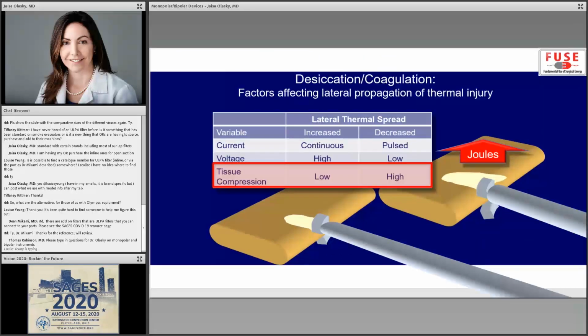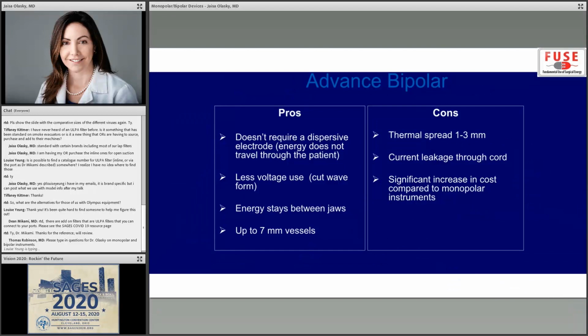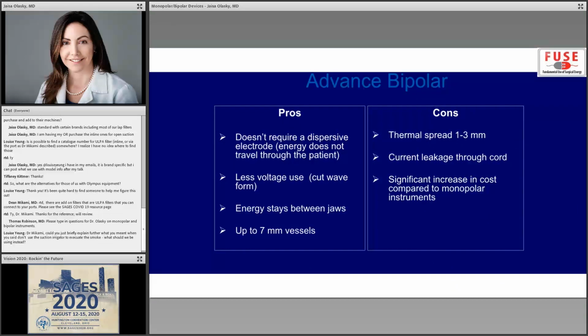In the interest of time, I'm going to go to just some of our high-yield points on this. So advanced bipolar versus the monopolar instruments. Key things to think about. You don't need a dispersive electrode. Again, the energy doesn't need to get through the patient. You're using less voltage. You're in the cut form. The energy is staying between jaws.